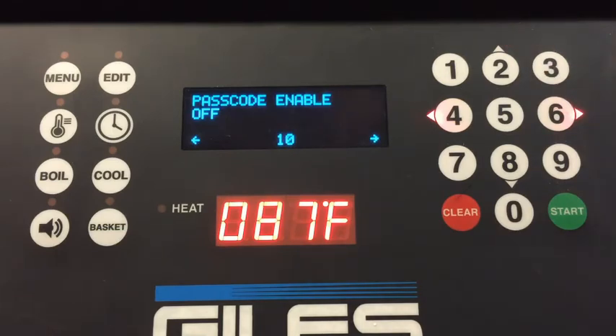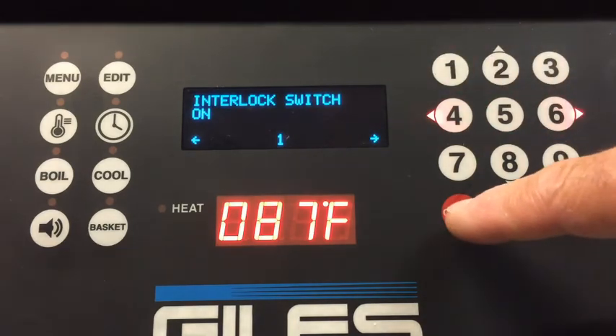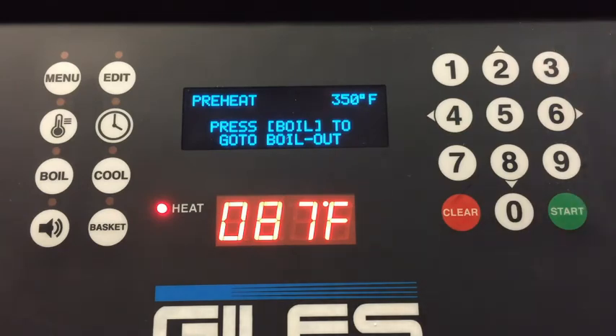Passcode enable. You can enable this to keep anybody from making any changes to the controller, including menu changes. They can change menus, they just can't go into the individual menus and make any edits, or go into any of the settings that we've been looking at here. If you choose to do this, make sure that you contact Giles Tech Service at 1-800-554-4537, option 1, to get what the passcode is. You'd like to know that before you go ahead and enable it. And then we're back to our interlock switch. And clear, again, will get you out.